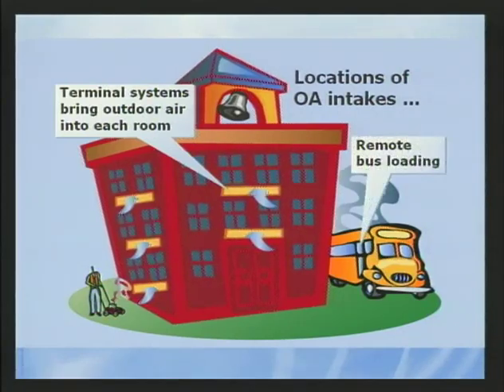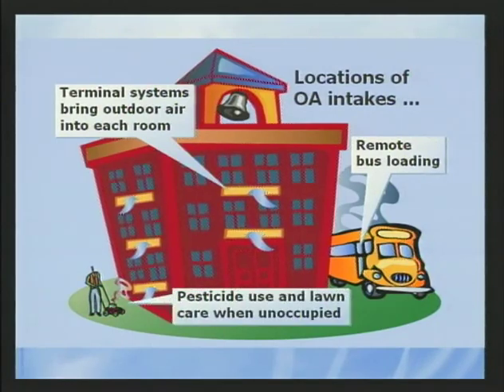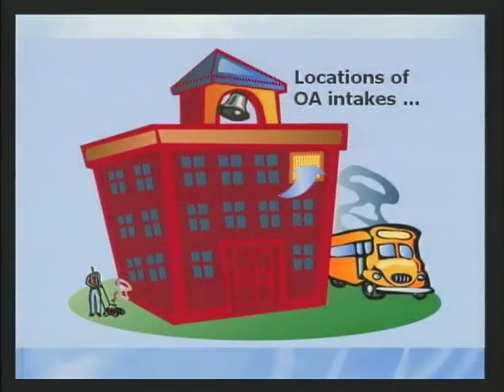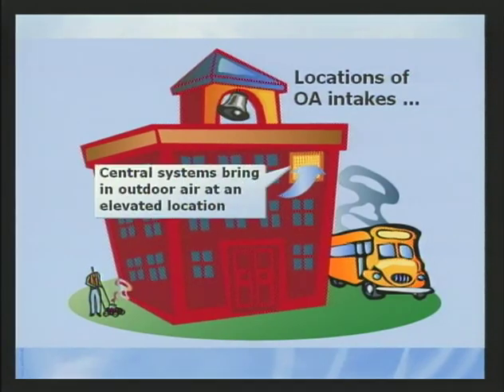Solutions such as remote bus loading, allowing pesticide application and lawn care only during unoccupied periods when the outdoor air intakes are closed, or even paving small areas immediately beneath the outdoor air intakes can greatly reduce the potential for bringing these contaminants inside. With central systems, outdoor air is typically brought into the building at a fewer number of locations around the building, typically high on a sidewall or through the roof. The fewer number of entry points and their elevated location makes them less susceptible to ground-level pollutants. However, even roof-mounted intakes must be carefully located to avoid entrainment of exhaust air from bathrooms, locker rooms, or kitchens that may be in the vicinity of the intake.